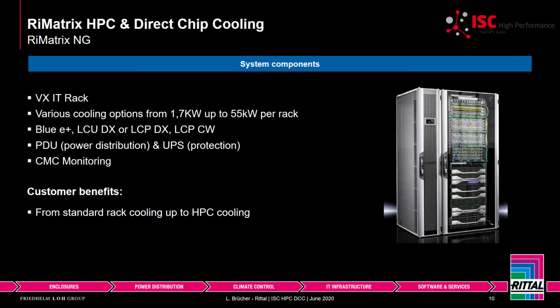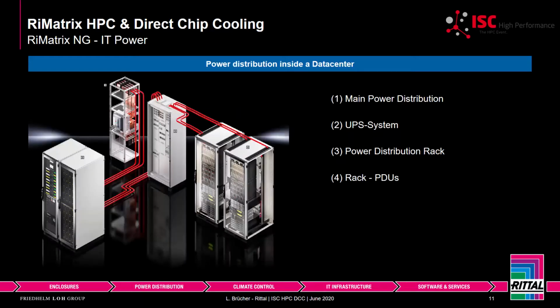To cool this rack, we have different solutions ranging from 1.7 kilowatts up to 55 kilowatts per rack. We have small cooling equipment like the Blue e+ for a manufacturing hall, an LCU which is an in-rack cooling solution, and LCPs to cool a rack row, typically in a hot and cold aisle setup. We also have PDUs, UPSs, and software to monitor high performance cooling.